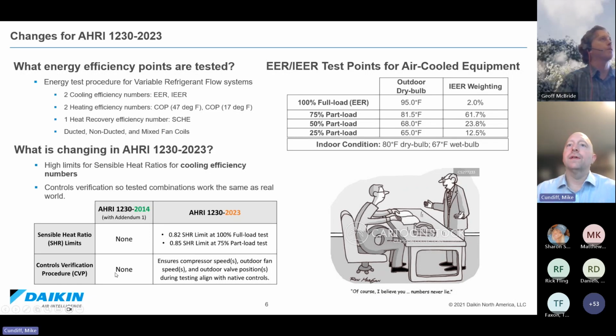On the controls verification side, there are standards in place and actual spot checks being done to ensure that the compressor speeds, the outdoor fan speeds, and the outdoor valve and indoor valve positions are the same as what you would find in a real life system that you would buy and put into a building.